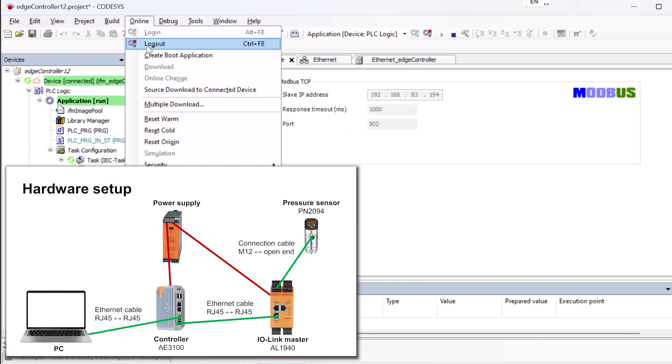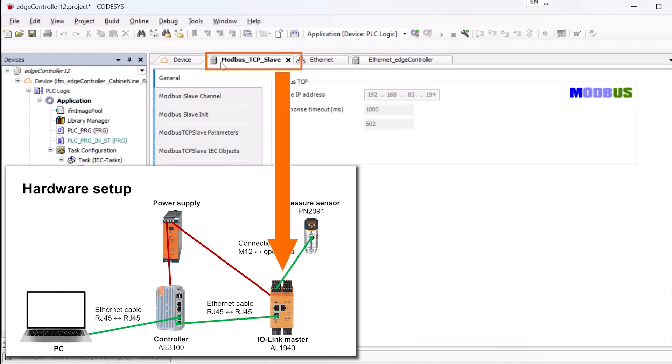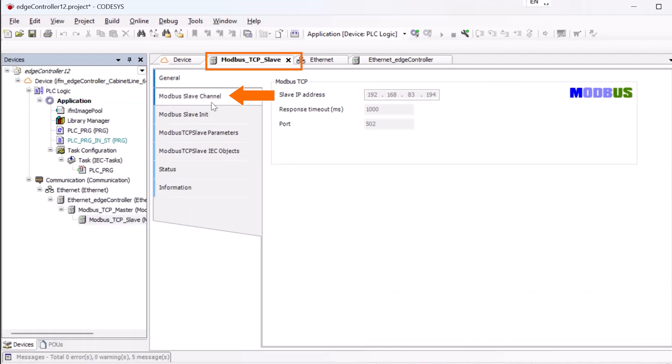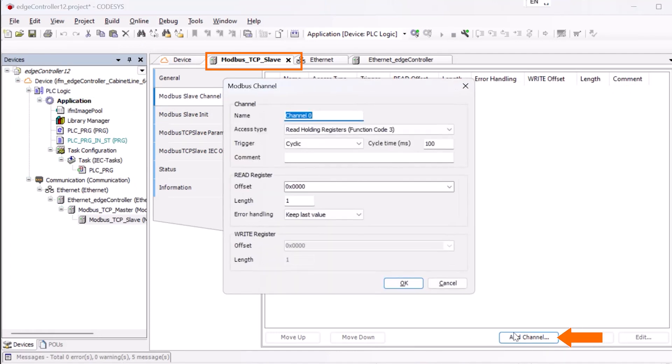To configure the port, we first have to log out and select our Modbus TCP slave, which is our IO-Link master AL1940. We select the Modbus slave channel and add a new channel to write parameter to the master. In order to do this, we need to configure the channel first.